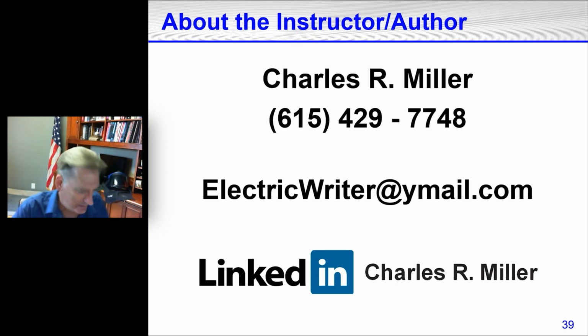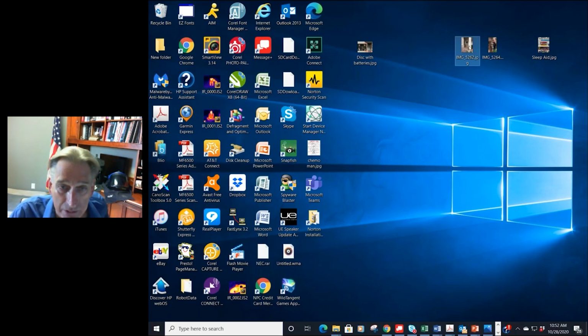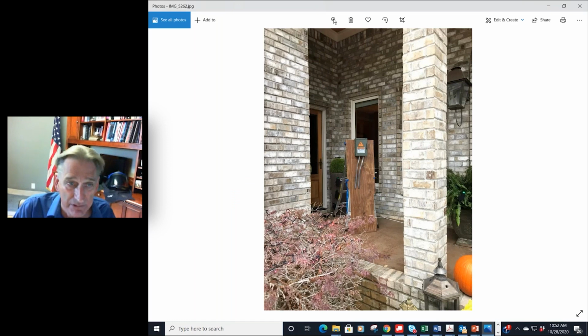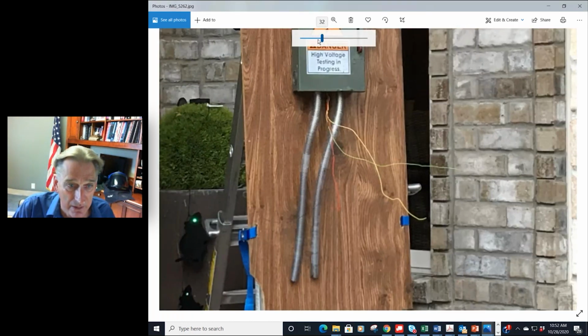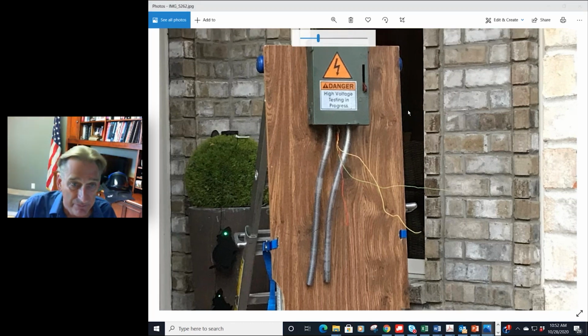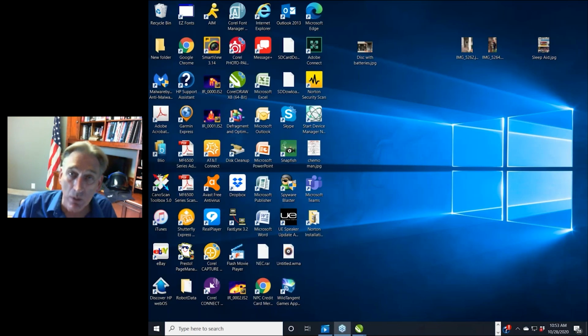Before I get into the questions here, let me show you something else. All right, a while ago, I was talking about evidence of impending failure. I've got a disconnecting means. Looking at that disconnecting means, is there evidence of impending failure? And hopefully everybody is saying, yes, there is evidence of impending failure. So what that means is in order to turn that disconnect on or off, I would have to be wearing arc rated clothing. I'd have to be suited up.